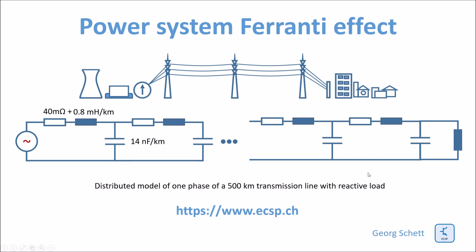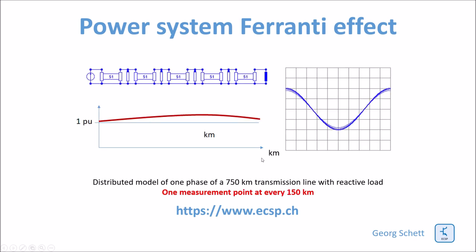Let's now look at what happens if instead of a resistance I put a reactor at the end of the line. With a reactor at the end of the same line, the voltage at the end decreases. If the reactor is optimized, the voltage is reduced to one per unit — meaning the same voltage at the source as at the end. However, with a reactive load you can see that the voltage profile along the line is not flat at one per unit; it goes a little above, giving a kind of N-shaped voltage profile.